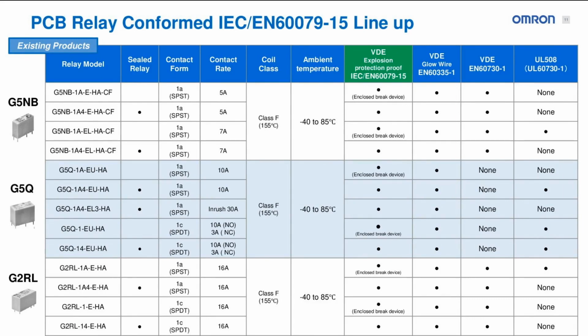Just to start over here on the right, we can see firstly that all of these conform to IEC-EN 60079-15. That's the explosion-proof rating. All of them also conform to the glow wire standard for anti-flammability in home appliance applications, and then there is a spattering of different safety standards further on the right columns. This will be for your reference since you'll have this presentation after the webinar.